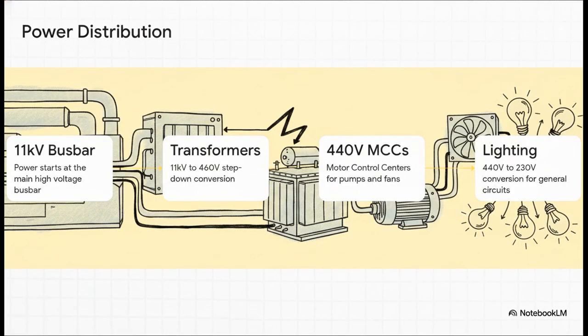Follow the literal path the electrons take from the massive generators down to a simple light bulb. Step 1. It starts at the 11 kV main bus bar. Step 2. The power hits those 3200 kVA step-down transformers. Step 3. The voltage moves into the 440-volt motor control centers, or MCCs, which distribute power to individual pump and fan motors across the vessel. And finally, Step 4. For general circuits, it steps down again through lighting transformers to a very familiar 230 volts.